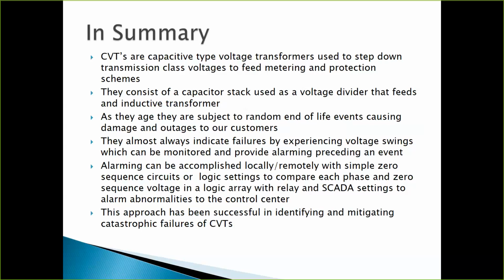All right, they consist of a capacitor stack. We talked about how they're made. They got a capacitor stack that acts as a voltage divider that feeds an inductive transformer at the bottom. The good news here, they almost always indicate failures by experiencing voltage swings, which can be monitored and provide alarming preceding an event. We can exploit the fact that they do this. Key here is preceding an event. That's the goal. We want to prevent this from a catastrophic failure, so we can do that.